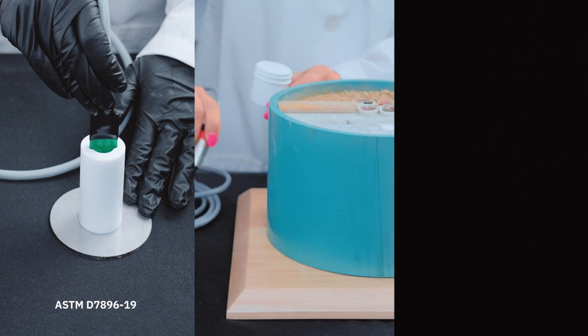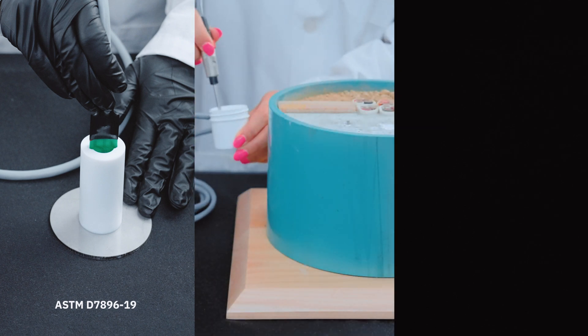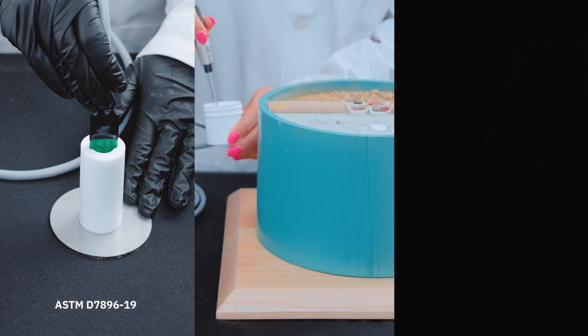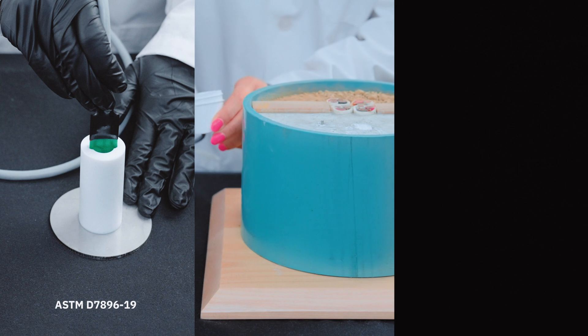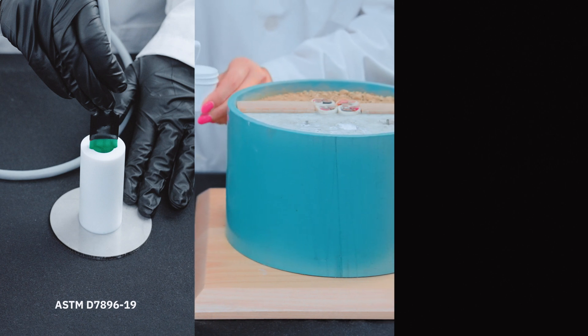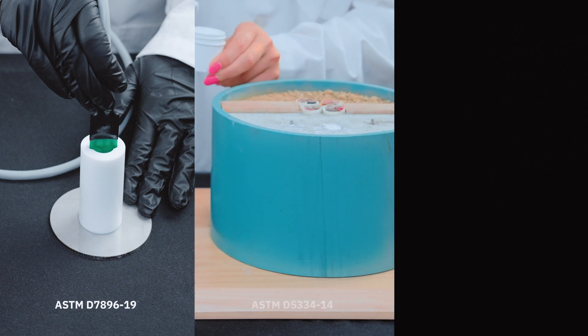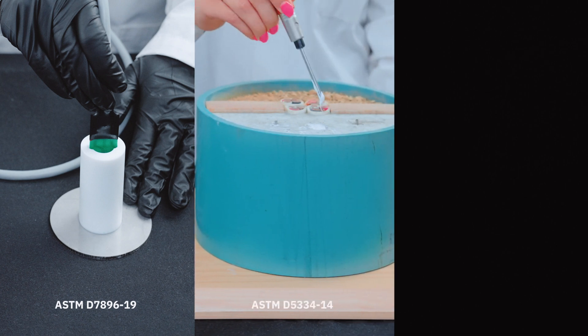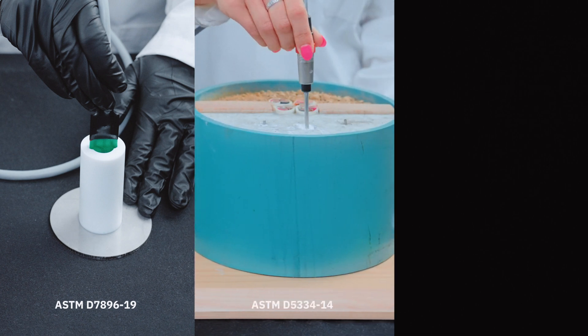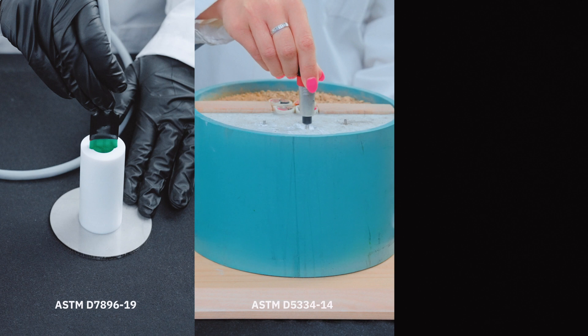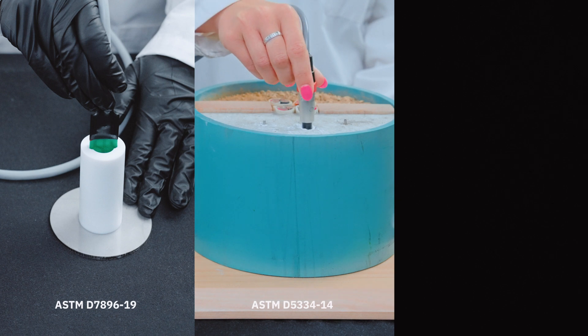The 50 millimeter transient line source sensor is designed for testing rigid materials like rock and concrete. A 4 millimeter diameter hole is drilled and the sensor inserted.